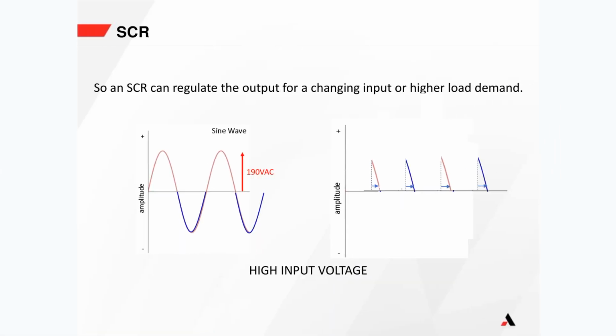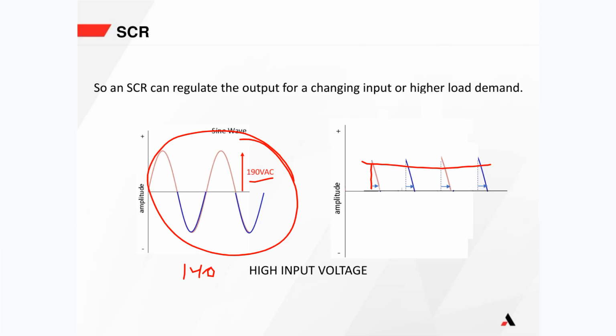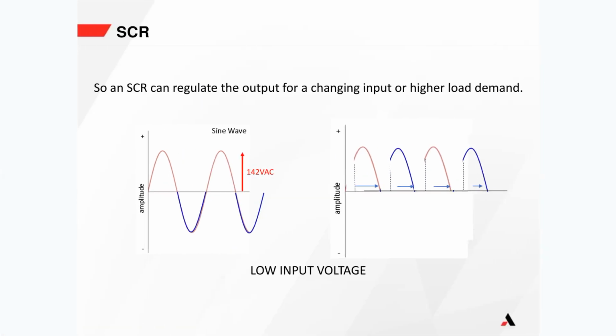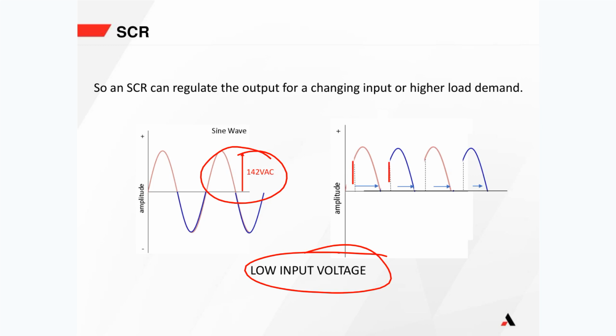So if we had a high input voltage, say up to 140 volts, the peak would be 190 volts, which would overcharge our battery. So we switch the SCRs on really late in their cycle, and the average would be lower. And if we had a low input voltage, with peak voltage down to 142 volts, we would switch the SCRs on much earlier in their cycle to keep the same average voltage.